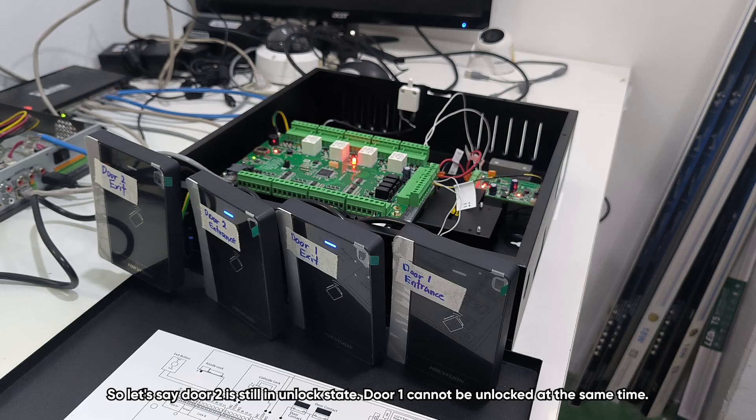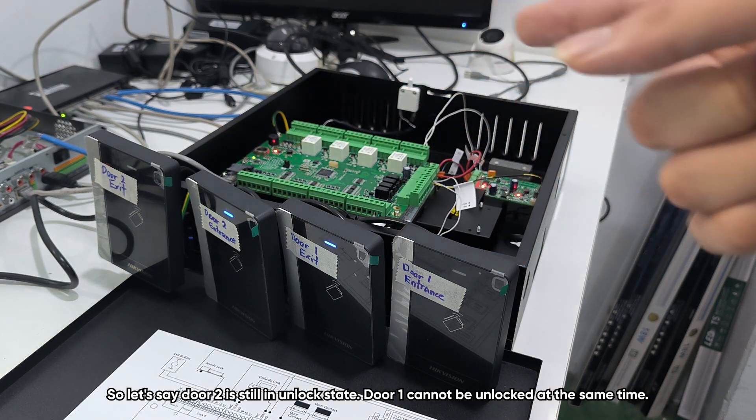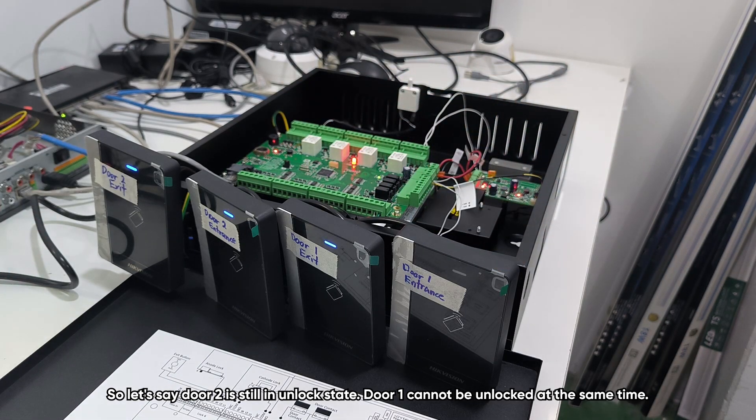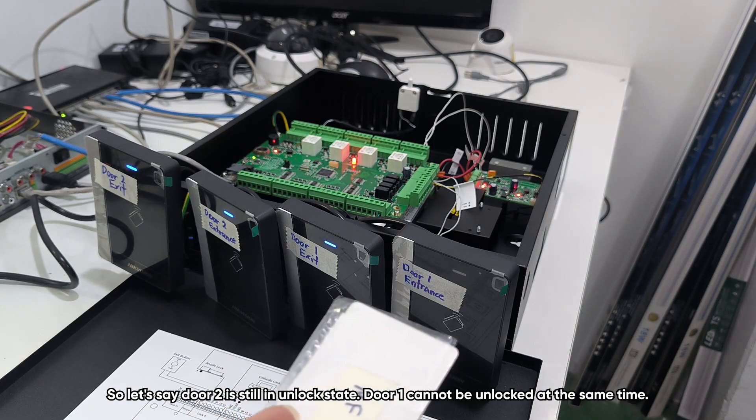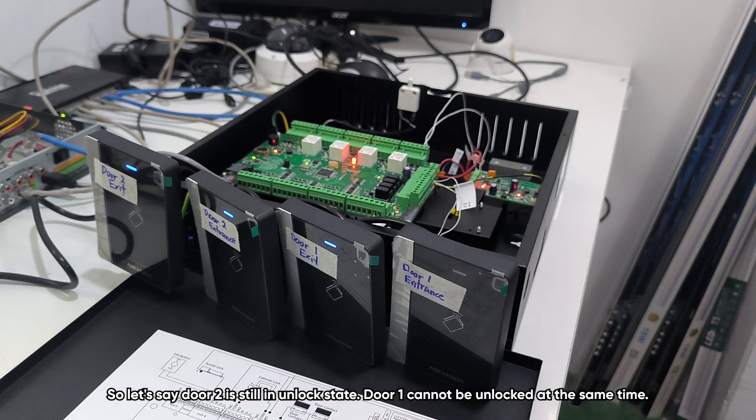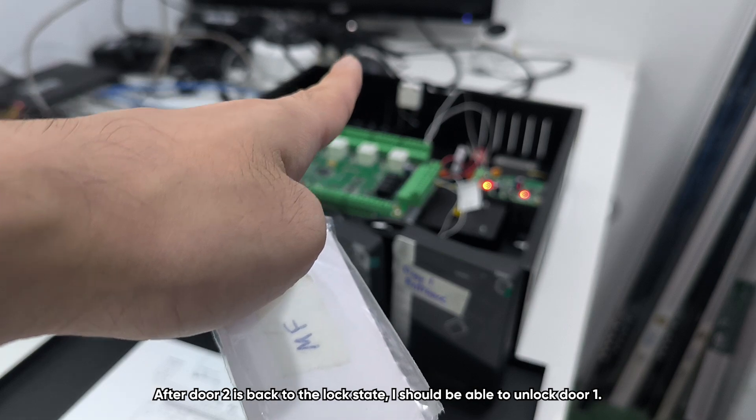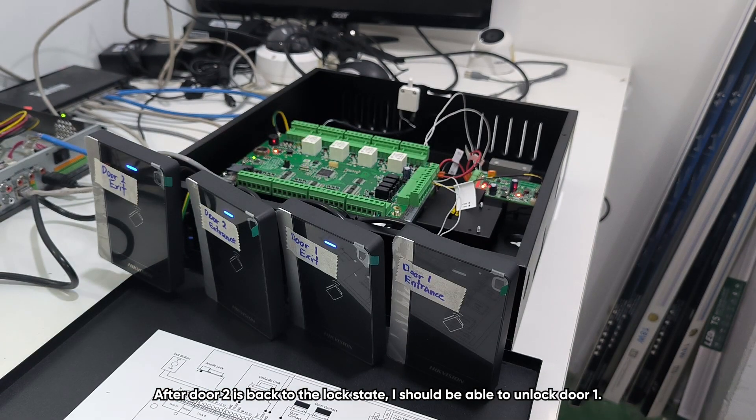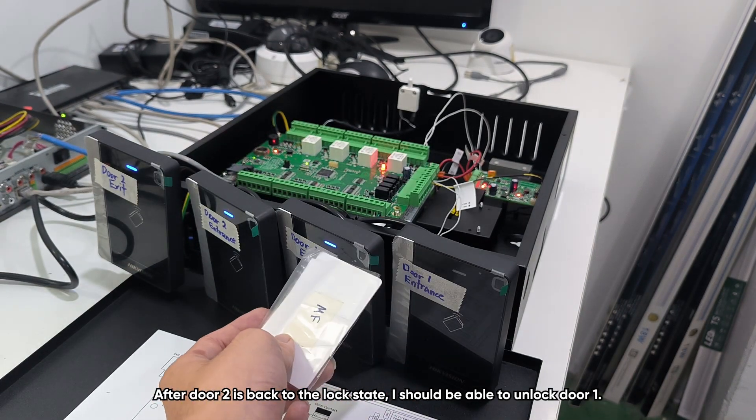So let's say door two is still in unlock state, door one cannot be unlocked at the same time. After door two is back to the lock state, I should be able to unlock door one.